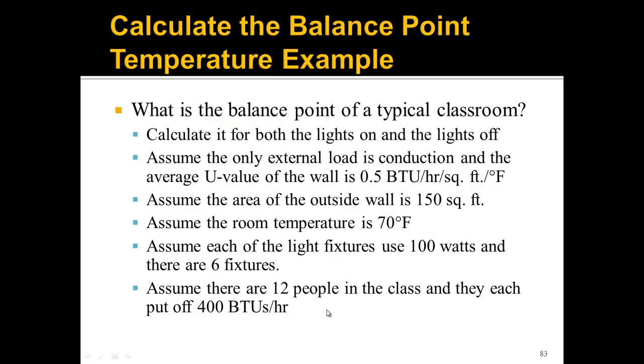Let's look at a typical classroom example. We're going to calculate the balance point for both lights on and lights off. Assume the only external load is conduction, the average U-value of the wall is 0.5 BTU per hour per square foot per degree Fahrenheit, and the outside wall area is 150 square feet. Assume room temperature is 70°F, each of 6 light fixtures uses 100 watts, and there are 12 people each putting off 400 BTU per hour.